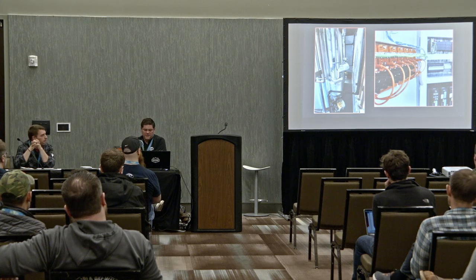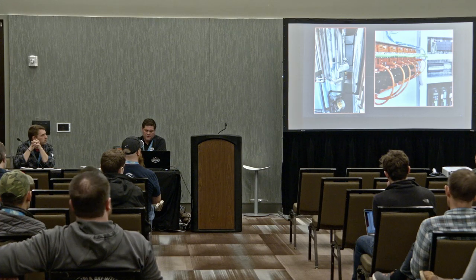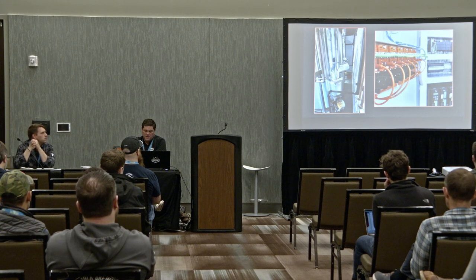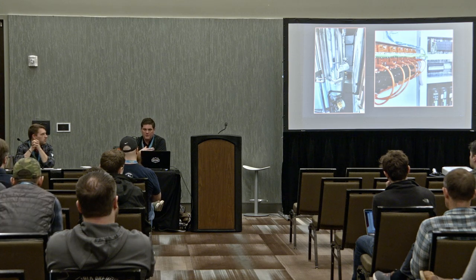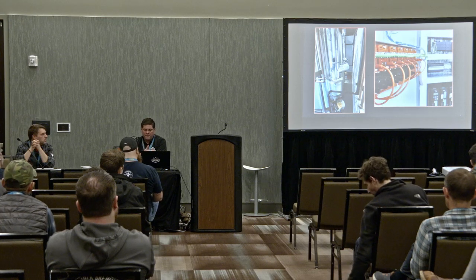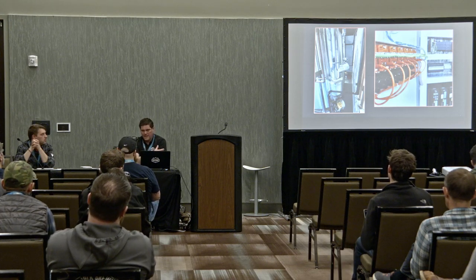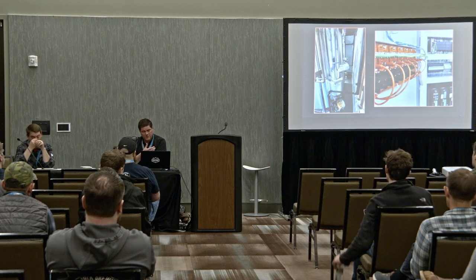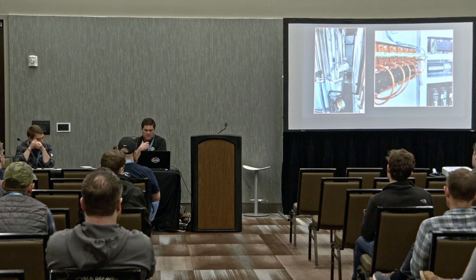Really showing electrical. This is inside one of our panels, so IFM effector, you know, this is all low voltage connectivity, and then the Siemens VFDs, so controlling your pumps, motors, and things like that. But this is what we do internally, but still you are working with a local trade. If your manufacturer is giving you a field wiring diagram, that's very important because then they are wiring your tanks, they're wiring your high voltage motors, your pumps, and then other low voltage connections being your lights, all of your cellar temp probes, your solenoids, and things like that.